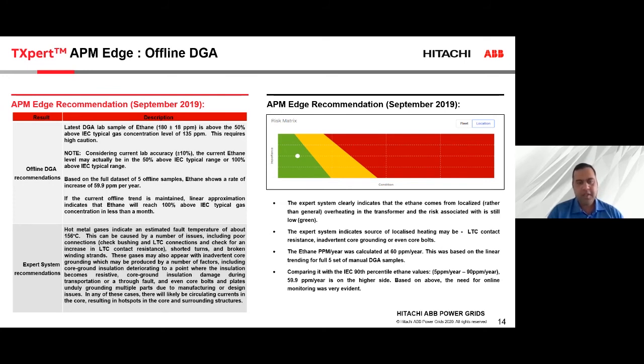And what did the expert system tell us? The expert system told us that the gases we are seeing in this transformer are hot metal gases. And the cause of this is basically either you have an unintentional core ground, or you may have other factors such as insulation deterioration. Basically, there will be circulating currents in the core which will result in a hotspot. And if you look to your right hand side, we calculated the risk associated with this transformer, and you will see that the risk of this transformer is in the green zone. That means the transformer can be operated.